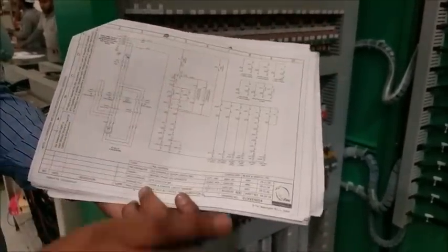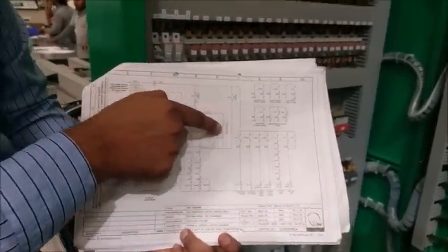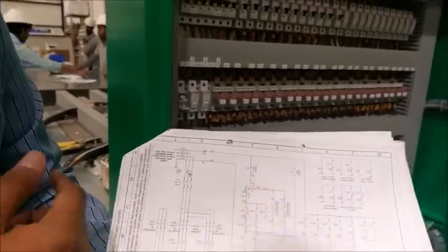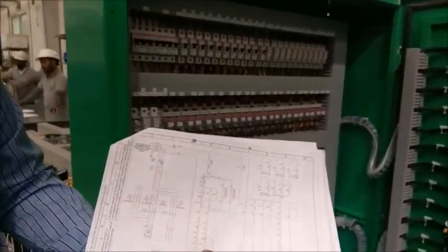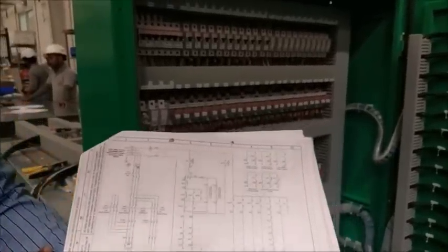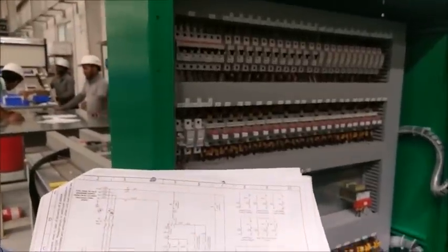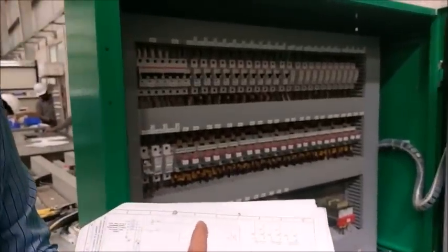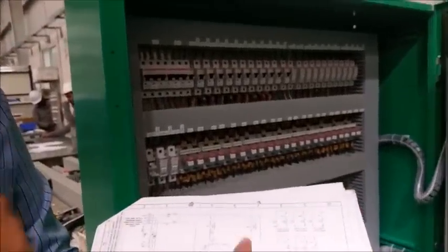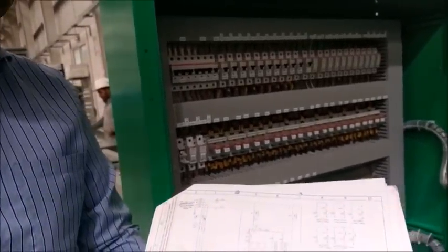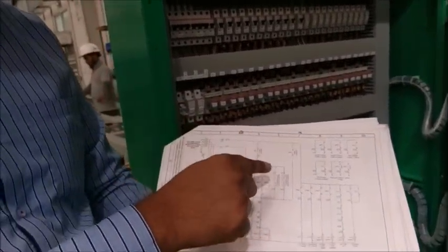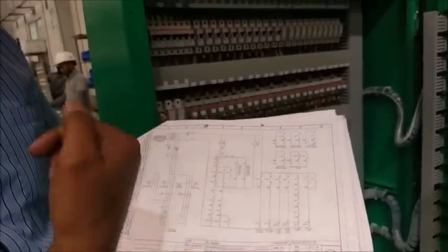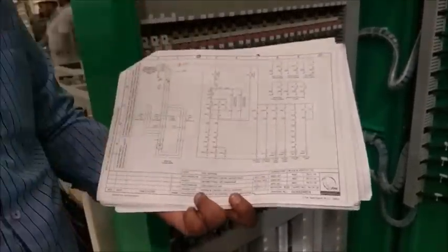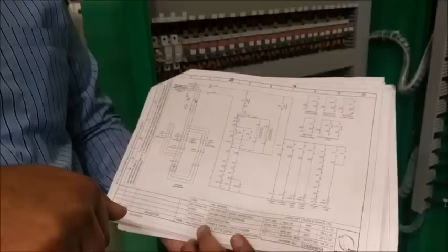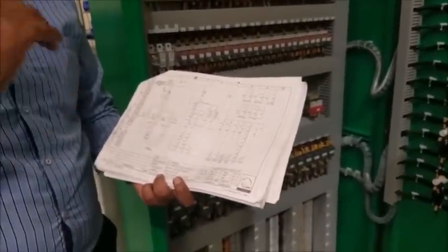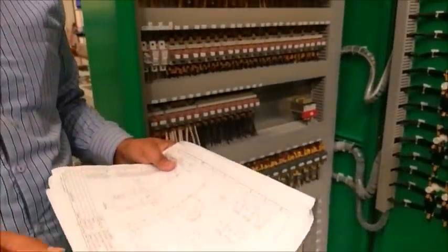In the normal condition, it will operate from BMS. So once this closes, this will be open, and then it will operate from here. To close this, it is from the fire alarm panel, not the override panel. In the same way, if there is an override interference, override will have topmost priority, then fire alarm. So override has priority over any panel, BMS or fire alarm.